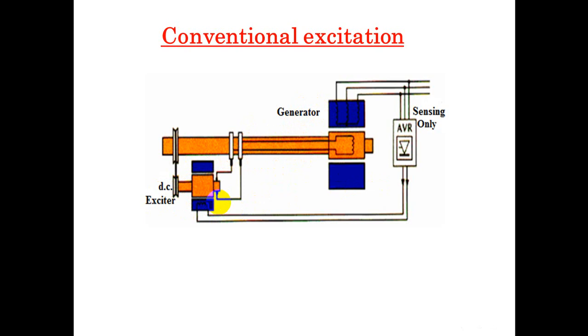The field current for the exciter itself, or the DC generator, is supplied by a rectifier bridge, itself piloted by the voltage regulator, or AVR, automatic voltage regulator, as shown in these pictures. This device is called the voltage regulator or AVR. Its function is to regulate the voltage of the DC exciter of the main generators. Note, at start of this unit, there is no voltage or no power from the main three-phase distribution in which the AVR is taking its energy.